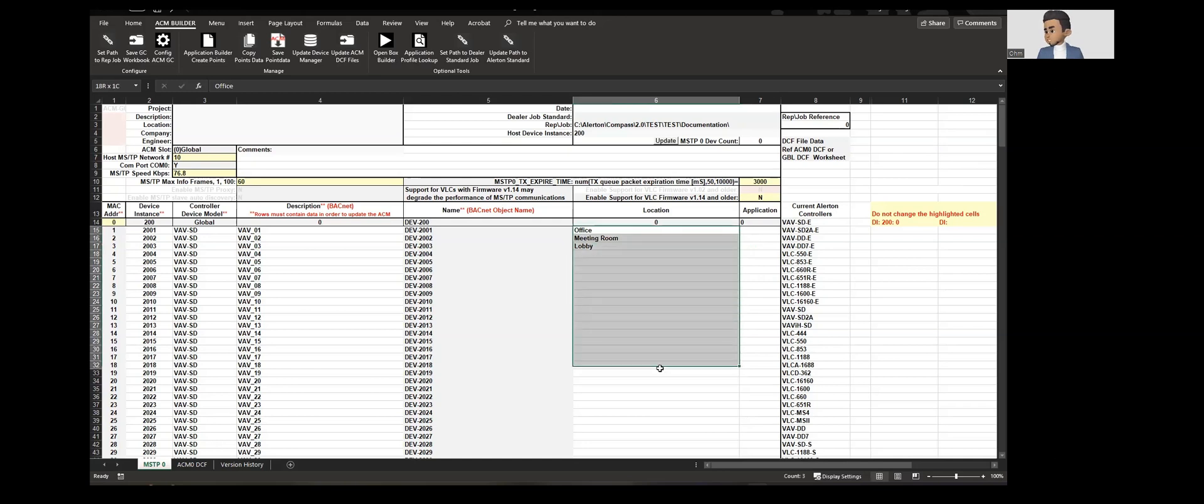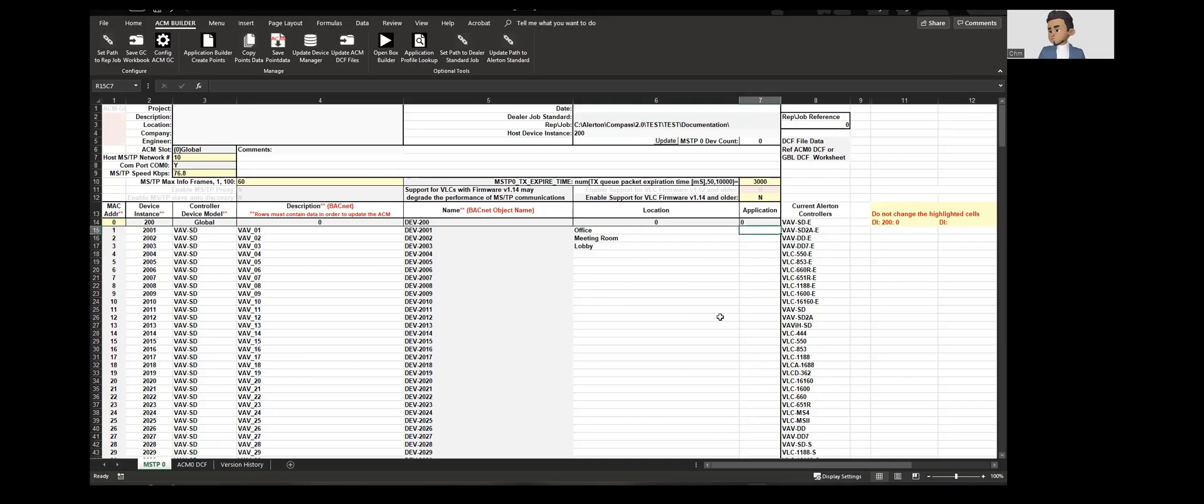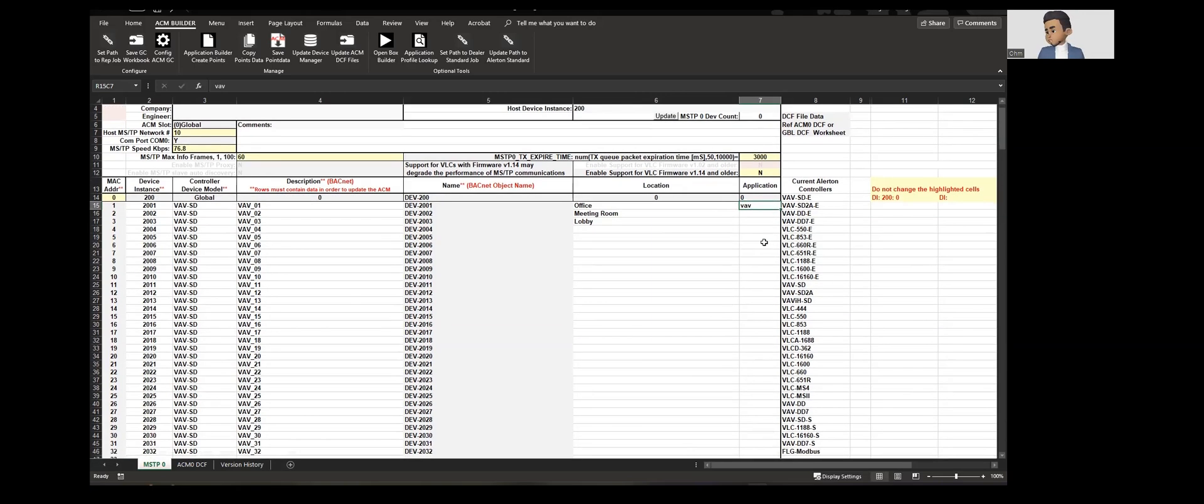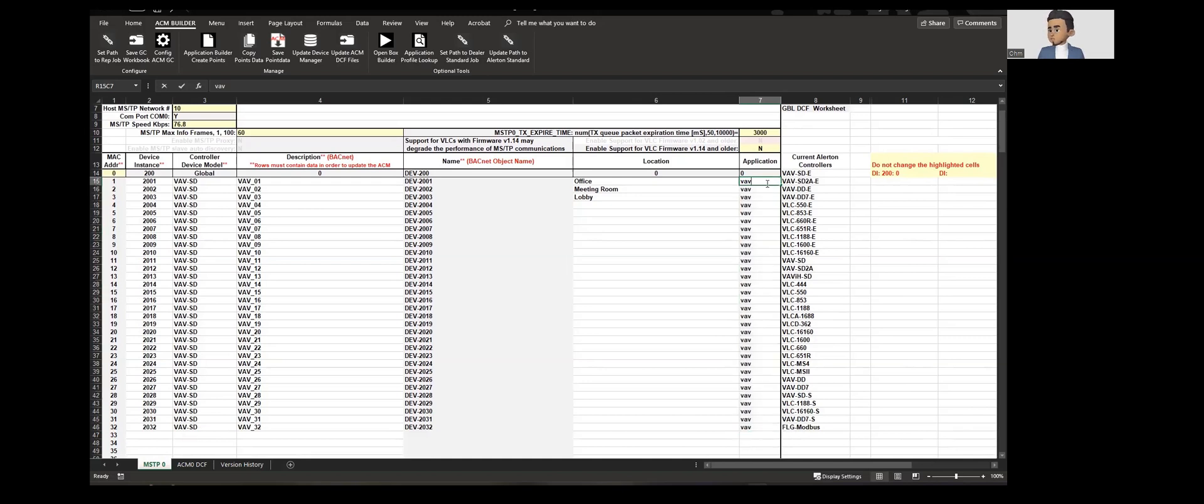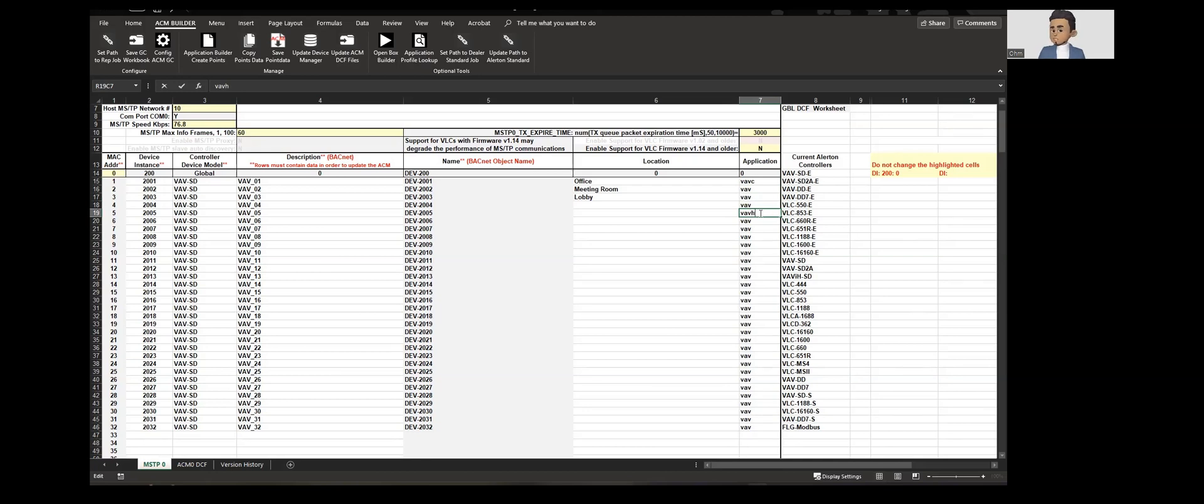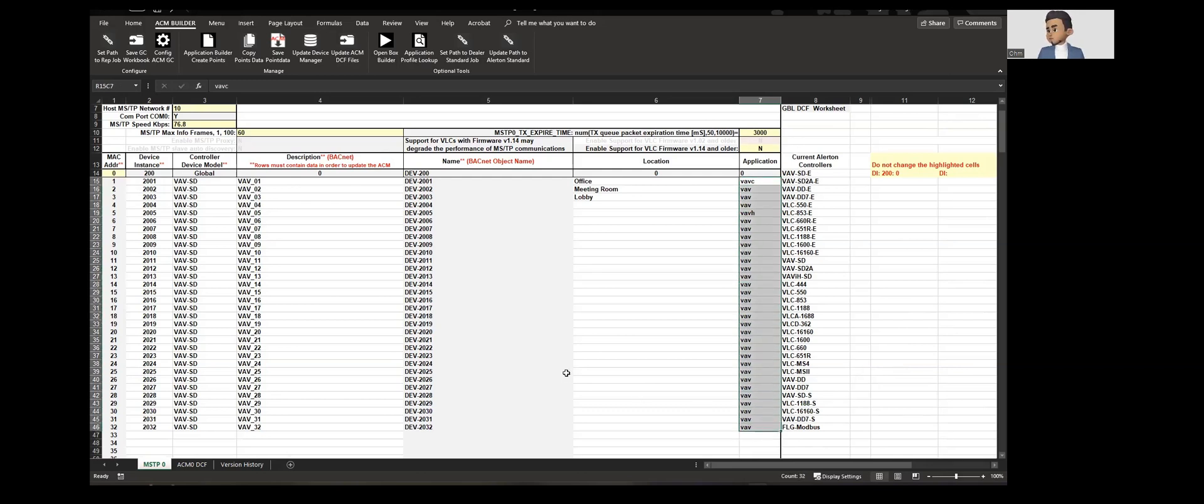Once we are in the application, let's say the DDC file name as VAV. You could choose VAV as your file name which is the DDC file name, or you can say VAVC for your cooling, and then let's say VAV5 has only heating then you can call the DDC file as heating and so on. You could define your program file here.